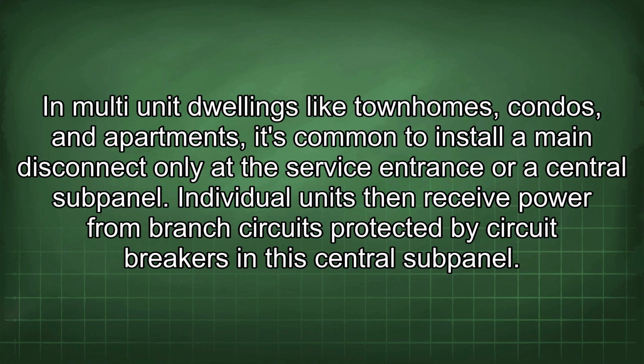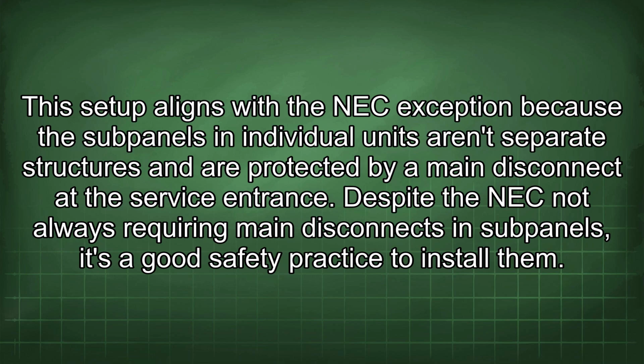In multi-unit dwellings like townhomes, condos, and apartments, it's common to install a main disconnect only at the service entrance or a central subpanel. Individual units then receive power from branch circuits protected by circuit breakers in the central subpanel. This setup aligns with the NEC exception because the subpanels in individual units aren't separate structures and are protected by a main disconnect at the service entrance.